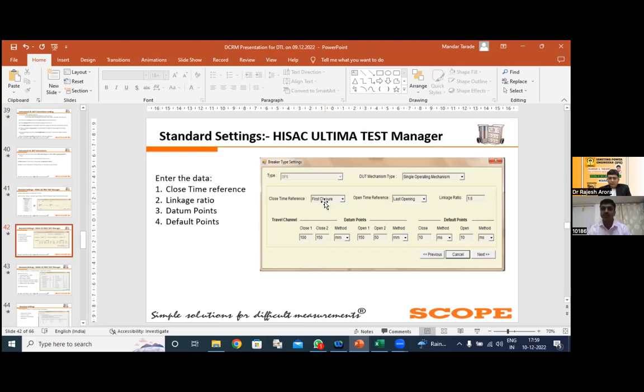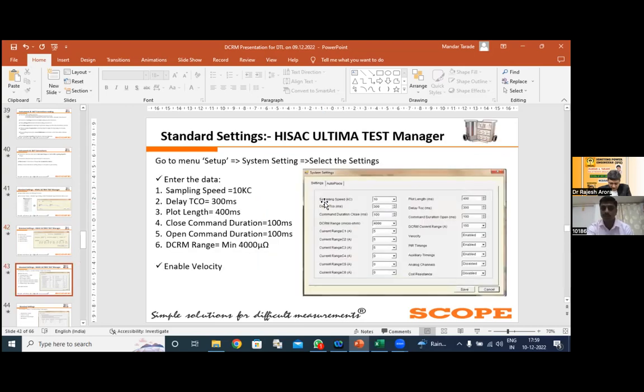Okay, so whatever data we are feeding here, with the help of that data, we are getting the results on our screen. These are some of the important settings which we need to follow at the time of performing the DCRM test. I have already told you the significance of the sampling speed equal to 10 kHz. The second important setting is the delay TCO: why we need to feed the delay TCO equal to 300 milliseconds. And the third important thing is that the plot length equals 400 milliseconds.